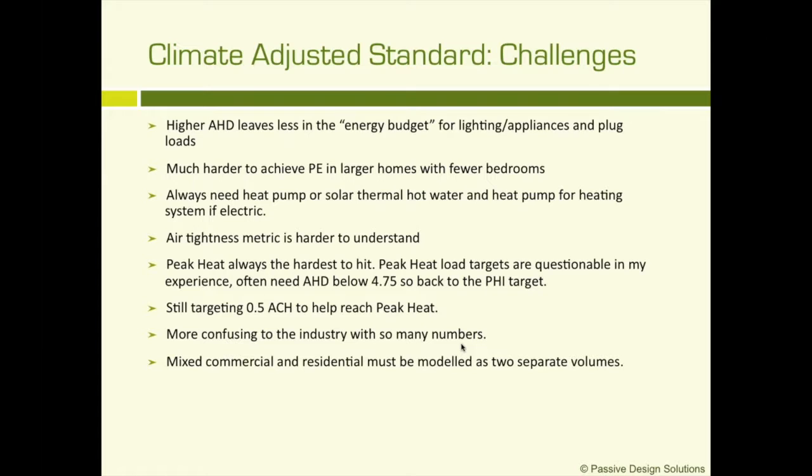We've been energy modeling a large number of projects and preparing a document to send into the PHIUS Tech Committee that makes an argument that in our climate, and we've modeled them in 7 climates in Canada, the annual heat demand usually has to go back down below 4.75 in order for us to hit the peak load.